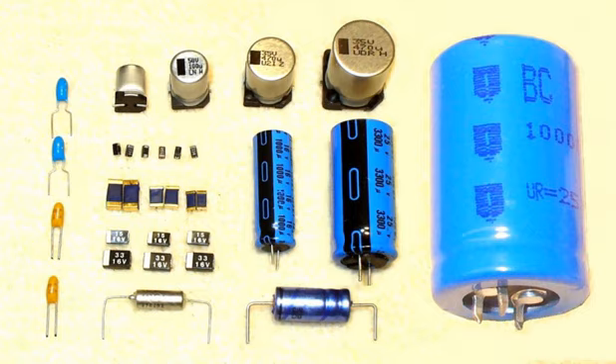The tested failure rates are often complemented with figures resulting from feedback from the field from big users concerning failed components, the field failure rate, which mostly results in a lower failure rate than tested. The reciprocal value of FIT is MTBF, mean time between failures. The standard operating conditions for the failure rate FIT are 40 degrees Celsius and 0.5 UR.